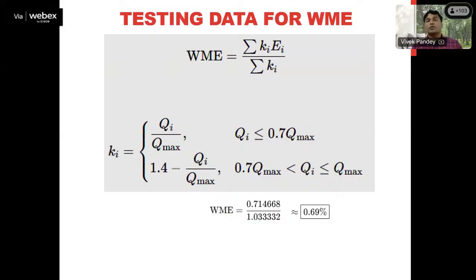That means, suppose in our example we have taken 5 testing points, so 5 flow rates we have decided. This formula will be expanded for 5 terms like K1 E1 plus K2 E2 plus K3 E3 up to K5 E5, divided by K1 plus K2 plus K3 plus K4 plus K5. Now, how will you get the values of K1, K2, K3, K4 and K5? That is an interesting thing.